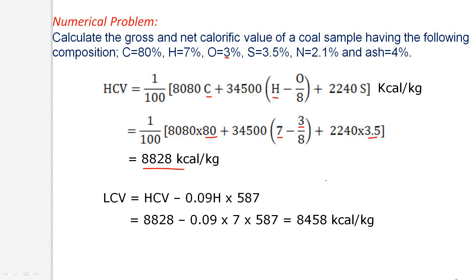When we know the HCV value, it is easy to calculate LCV using the formula: LCV = HCV − 0.09H × 587 kilocalories per kg. Substituting HCV = 8,828 and H = 7%, we obtain LCV = 8,458 kilocalories per kg. In this way, we can calculate the calorific value of any fuel using Dulong's formula when we know the constituents present in the fuel.